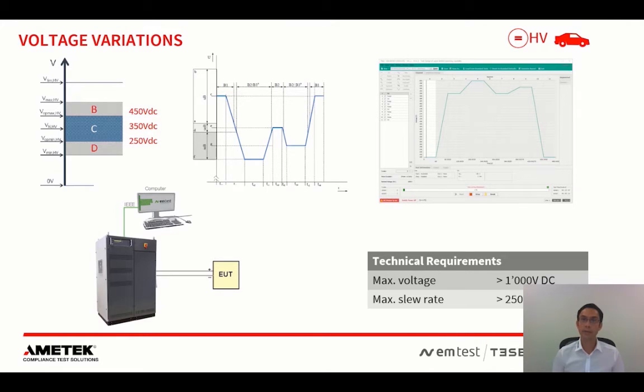The test equipment that is required is basically a DC source that is capable of providing very stable supply voltage, but is also capable of doing the fast transition times. Nowadays, the border of the nominal voltage is around 1000 volt DC. It might go in the future up to about 1500 volt DC. And the maximum slew rate for very fast signals might be 250 volt per microsecond. In the ISO 21498, actually, the fastest pulse that is defined has a 250 volt per millisecond slew rate.